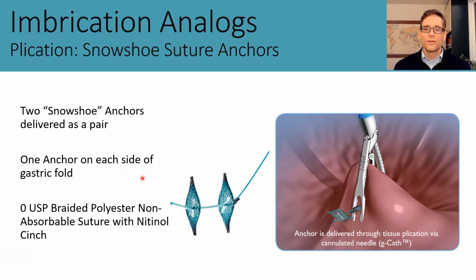The Snowshoe tissue anchors are seen more closely here, and you can see they're made of 0 USP braided polyester. They're non-absorbable, and they have a nitinol cinch. And here you see the tissue approximation device holding a full thickness piece of tissue. The hollow needle is passing through that tissue, and the distal tissue anchor is visible here. The needle will then be retracted, the device opened, and the second tissue anchor deposited on the proximal side. And then the 2 tissue anchors reside in the stomach on the mucosal surfaces. However, they're holding together this full thickness plication, pinching serosa to serosa on the back side here.